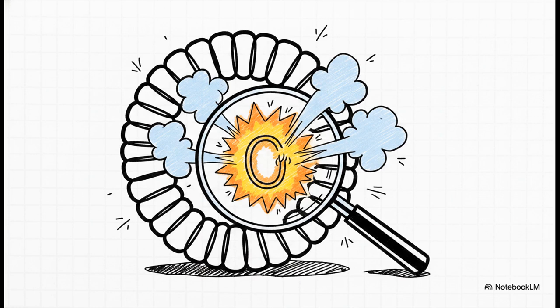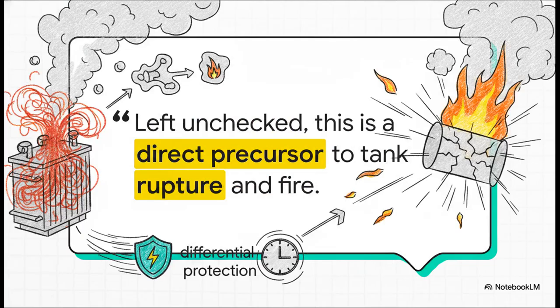A single shorted turn might represent less than 1% of the total winding, but it creates this tiny, localized loop of incredibly low impedance. So you get an intensely high circulating current trapped entirely within that tiny loop. Standard overcurrent relays on the main lines are completely blind to it, but inside, intense heat is rapidly building up. If you don't catch that hidden pressure cooker instantly, the consequences are literally explosive.